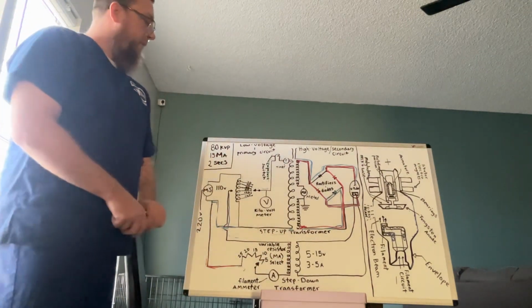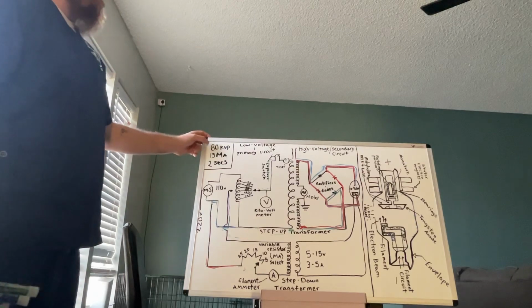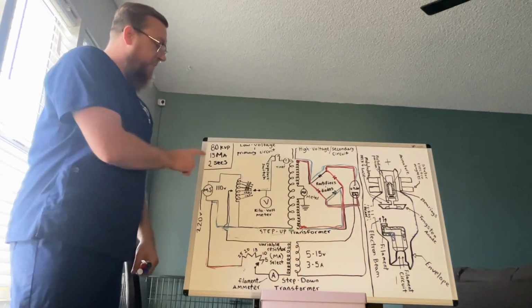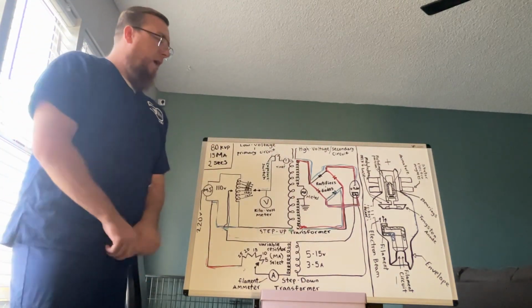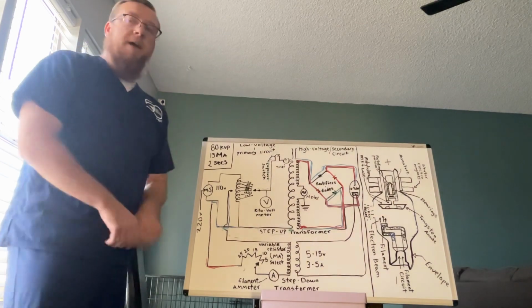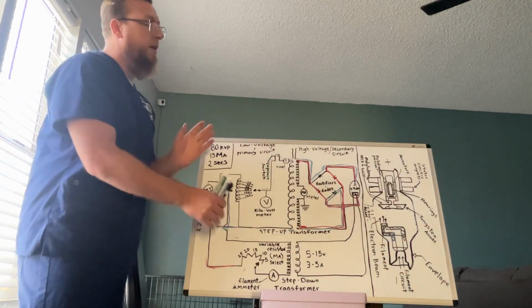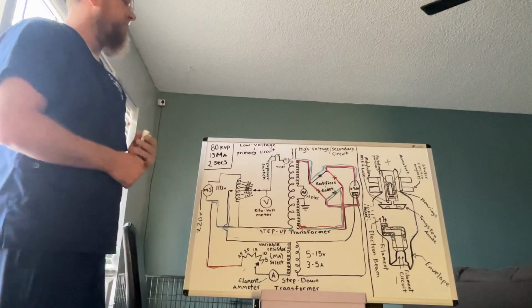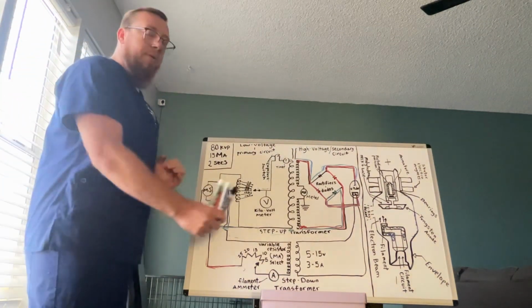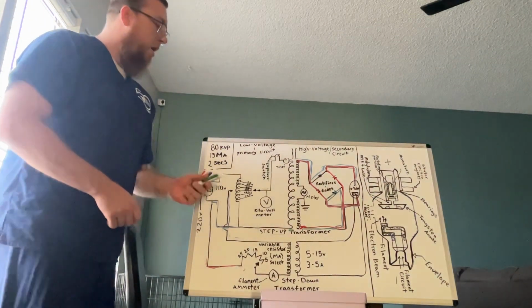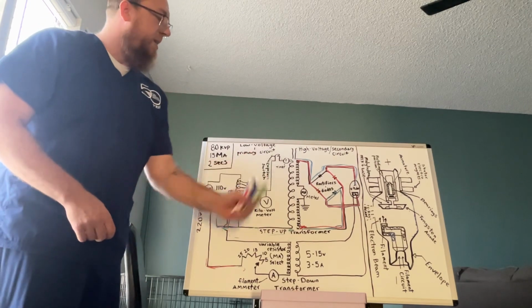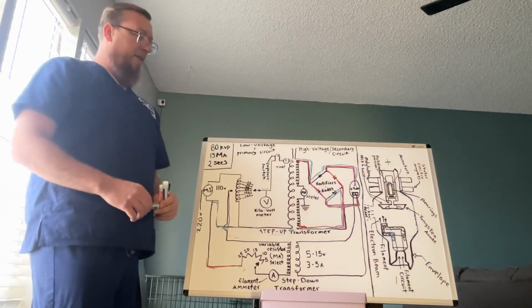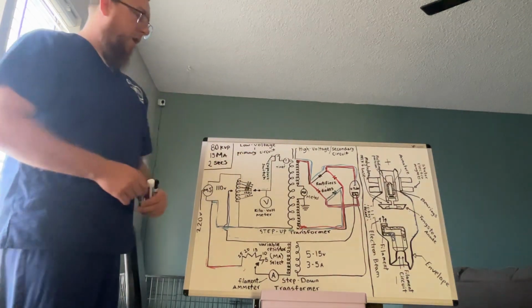I'm going to start off with an example of 80 kVp, 15 mA in 2 seconds. I'm going to enter these into my control panel, and it's going to set the X-ray circuit up for whatever needs to be done with it. As I go through, I'll explain all the different steps and different meters and so on and how they work.